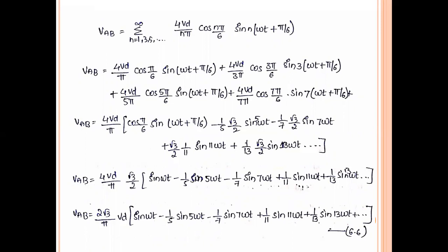If the motor operates under saturation, we know various disadvantages will happen. That also limits the motor speed to at least 40% of the base speed. Below 40% of the base speed, we cannot achieve good performance for the induction motor. So all these are the disadvantages when we use a stepped wave inverter.